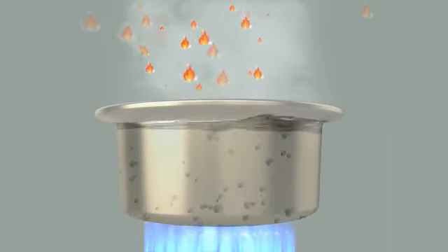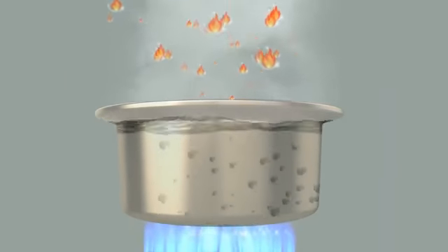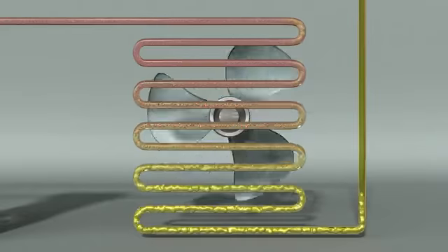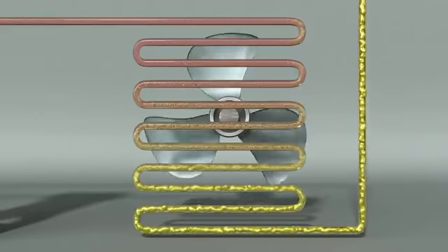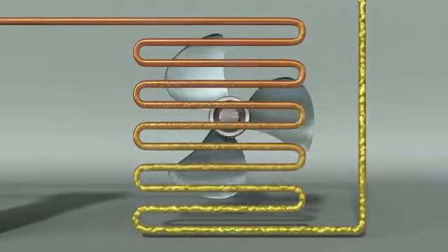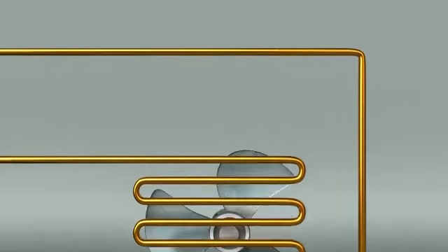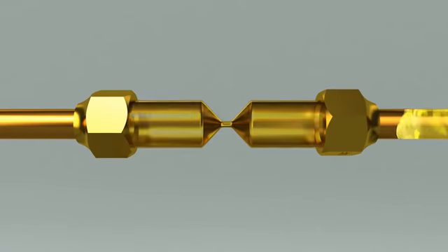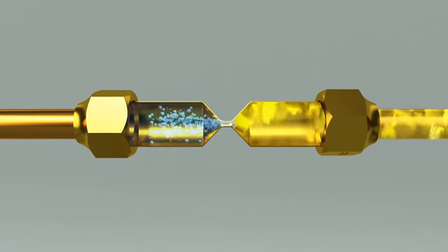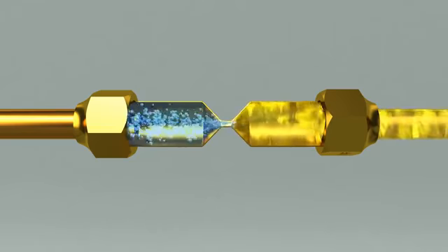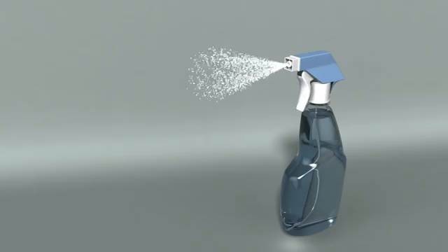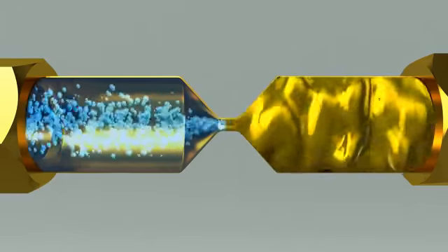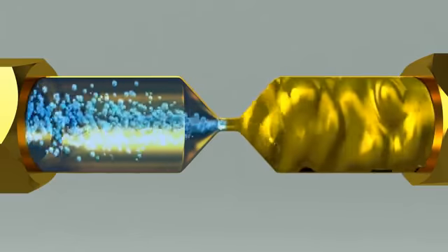While evaporation is the transition of liquid to gas through heat absorption, condensation is the transition of gas to liquid when it loses heat. A condenser serves to turn refrigerant in a hot gas state into liquid form by taking away its heat. The refrigerant passed through a condenser becomes liquid and flows into the expansion valve. There is a section in the expansion valve where the piping gets narrow, and as the refrigerant passes here, it splits up into many pieces. What we see here is similar to the principle behind water being spread from a spray. As the pressure on the refrigerant drops, its temperature drops dramatically as well.